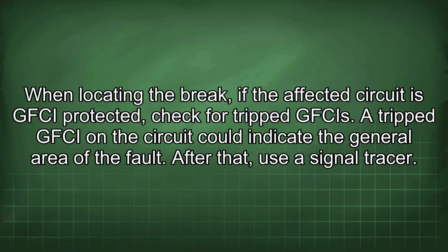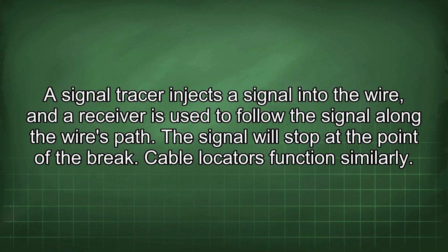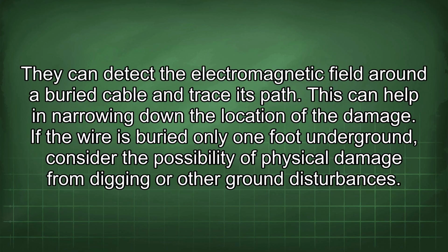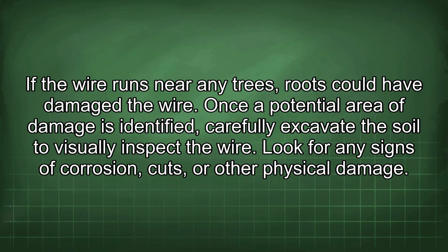After that, use a signal tracer. A signal tracer injects a signal into the wire, and a receiver is used to follow the signal along the wire's path. The signal will stop at the point of the break. Cable locators function similarly. They can detect the electromagnetic field around a buried cable and trace its path. This can help in narrowing down the location of the damage. If the wire is buried only 1 foot underground, consider the possibility of physical damage from digging or other ground disturbances. If the wire runs near any trees, roots could have damaged the wire.